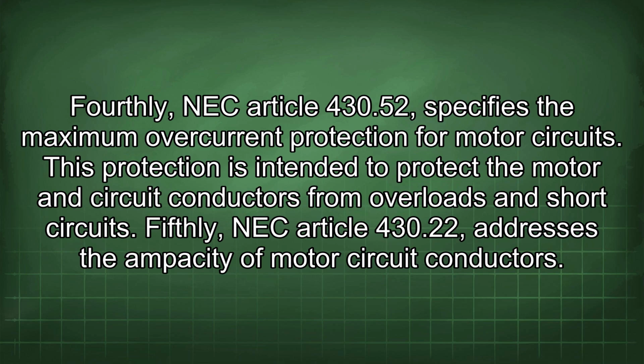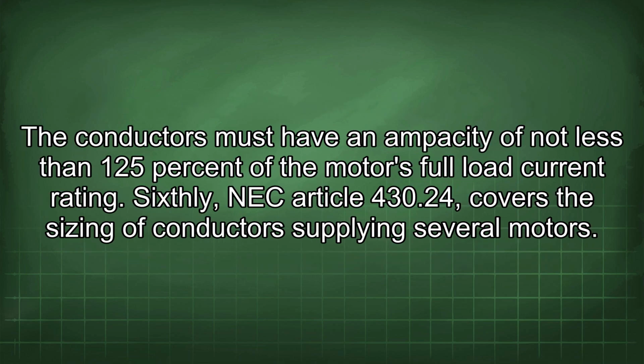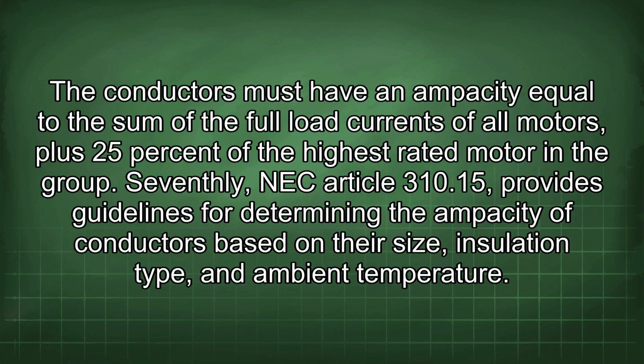Fourthly, NEC Article 430.52 specifies the maximum overcurrent protection for motor circuits. This protection is intended to protect the motor and circuit conductors from overloads and short circuits. Fifthly, NEC Article 430.22 addresses the ampacity of motor circuit conductors. The conductors must have an ampacity of not less than 125% of the motor's full load current rating. Sixthly, NEC Article 430.24 covers the sizing of conductors supplying several motors. The conductors must have an ampacity equal to the sum of the full load currents of all motors, plus 25% of the highest rated motor in the group.